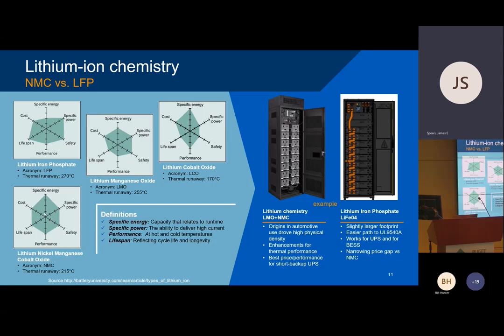The other common chemistry, becoming more common today especially for its extra resistance to thermal runaway, is lithium iron phosphate, abbreviated LFP. Five years ago, lithium iron phosphate was about 30% more expensive and also about 30% larger than other lithium choices, and those two strikes basically put it out of the game for a couple of years. But vendors have narrowed that gap significantly, so the price is now pretty close, and the power density is almost as good as the other choice. It also has notably more resistance to thermal runaway, making it easier for those batteries to pass a UL 9540A flame test, etc.